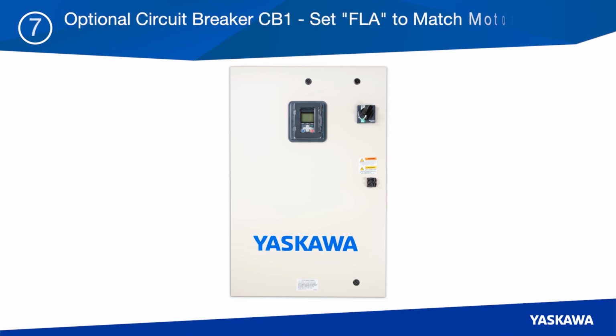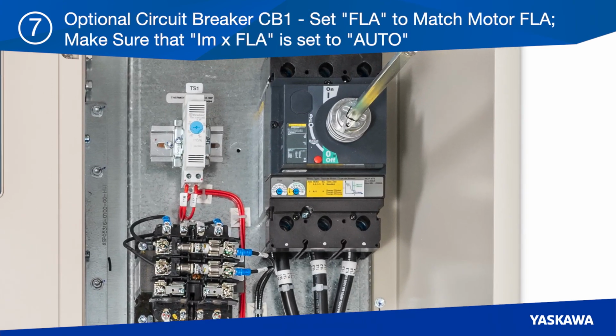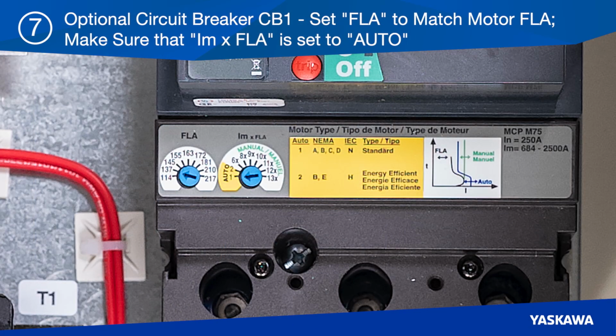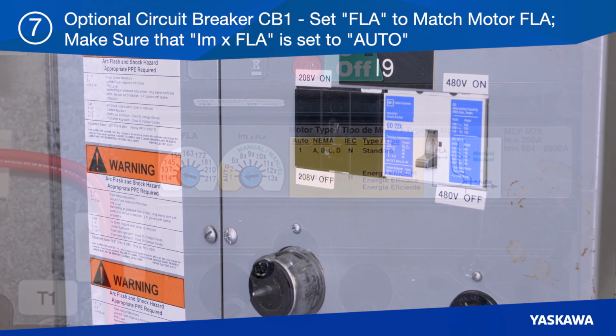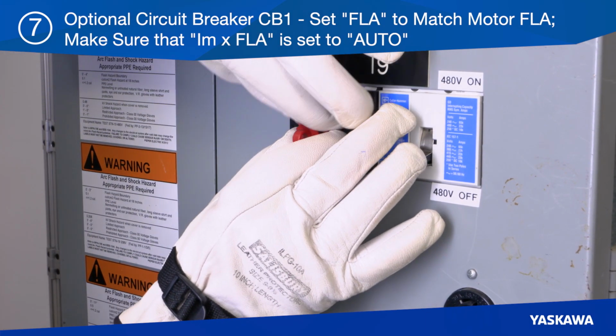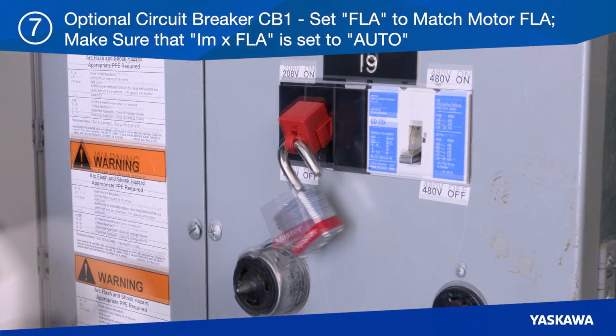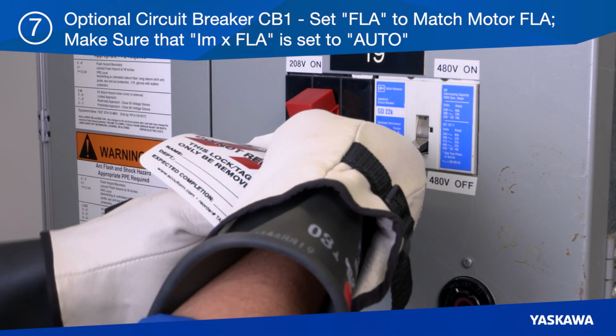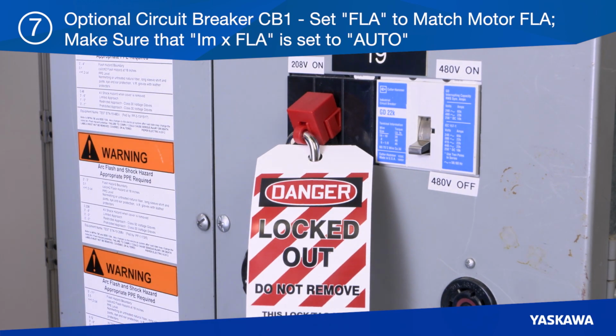Step 7 is optional if the CB1 circuit breaker option is installed. Adjust the FLA dial to the motor nameplate FLA and adjust the instantaneous trip point setting dial to Auto 1 Standard or 2 Energy Efficient depending on the motor type. Confirm that all power sources are turned off and you have performed the correct lockout-tagout procedures before doing any wiring.